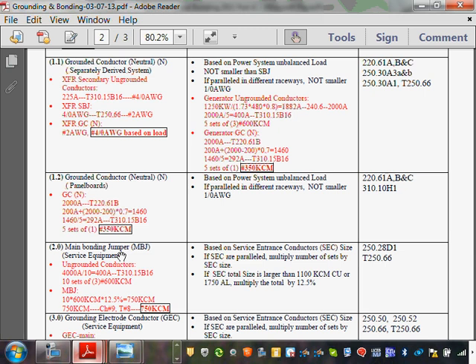So it gets a little bit complicated, but I came up with this size, which is okay for overhead, even though we're coming from underground here, just for sizing. 10, I have 600 kcmil. Then you take the same 10 multiplied by 600, 12.5%, that will give you 750. And 750, Chapter 9, Table 8, you will verify, do they make a 750 kcmil, or do I have to sell an arm and a leg to custom design this cable for me? Yep, that's how you verify that they have 750 kcmil. So 750 kcmil is your main bonding jumper.